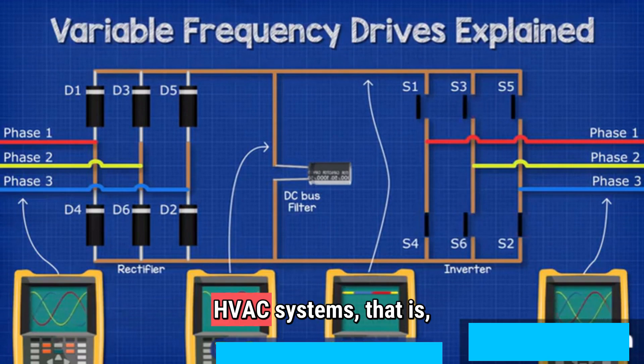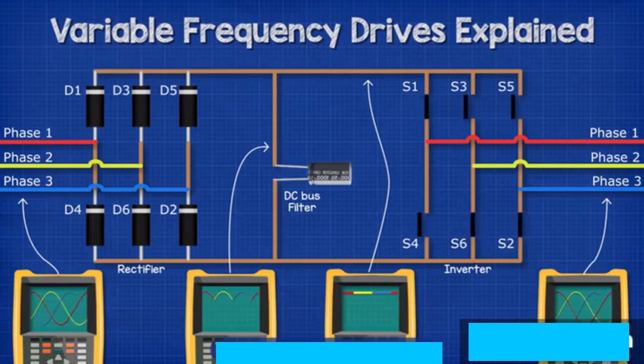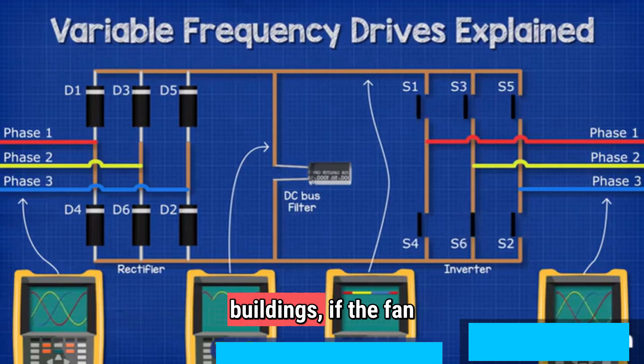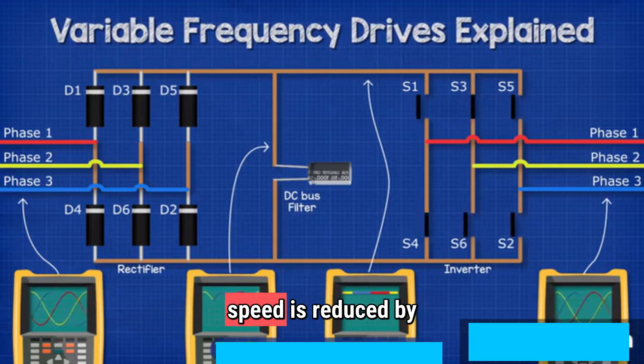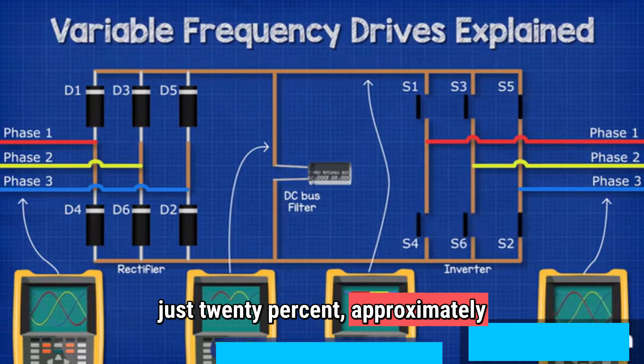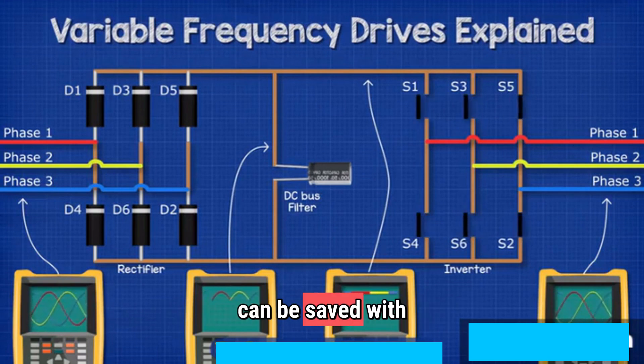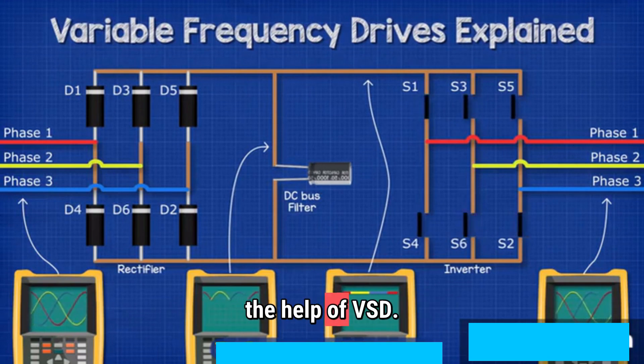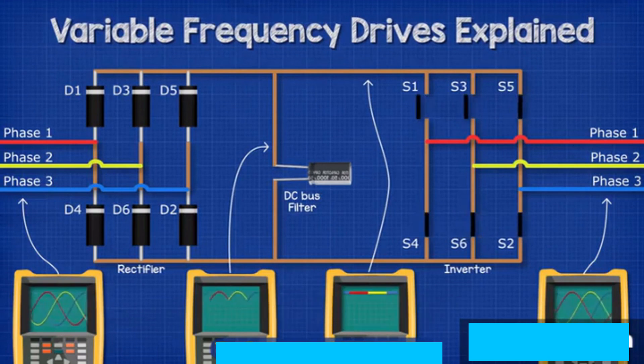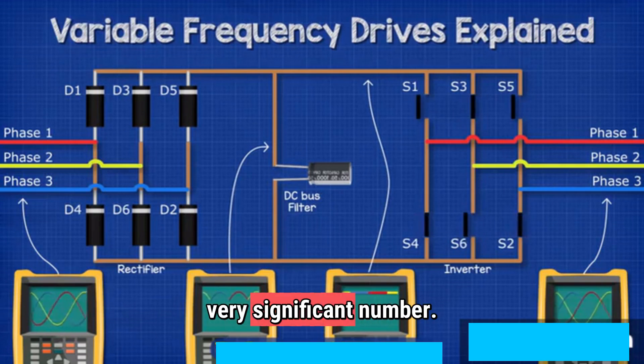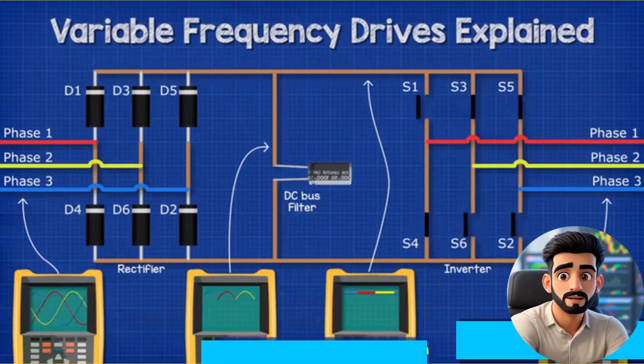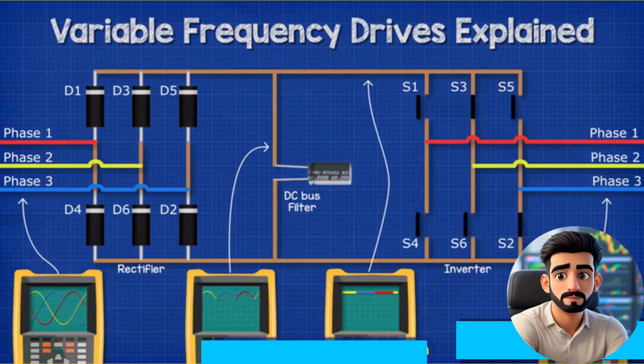You will be surprised to know that in HVAC systems — that is, cooling systems of large buildings — if the fan speed is reduced by just 20%, approximately 50% of energy can be saved with the help of VSD. 50% is a very significant number. Now you might be wondering how this magic happens. For this, we will have to look inside the VSD.